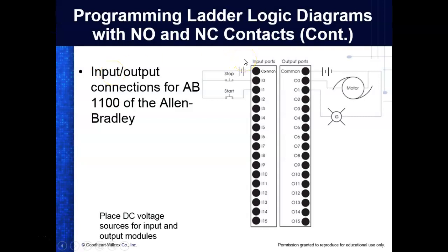So this would be an external power supply. Most of your PLCs have internal power supplies, but they're not intended to run a big load. So just about all the PLCs in the industry are going to run an external power supply. Because if you use a solid state sensor, which is very popular, these are electronic circuits and you have to power those up. And your PLC power supply cannot power 100 sensors, right? You understand that? So notice what I have here. So here's my power supply.